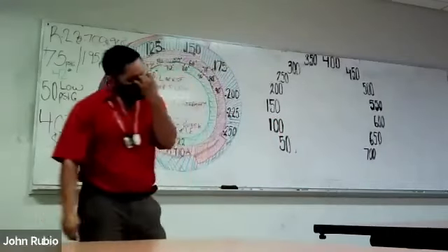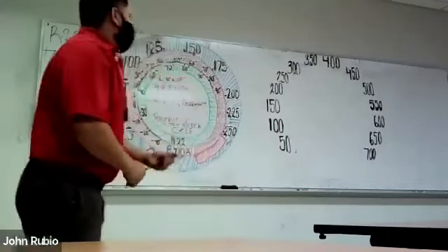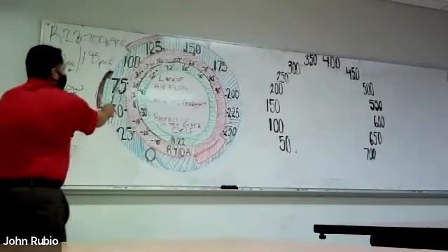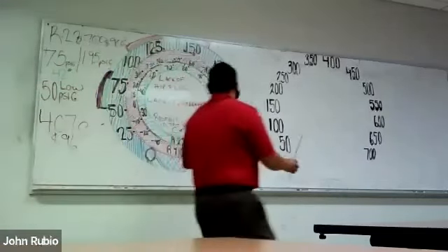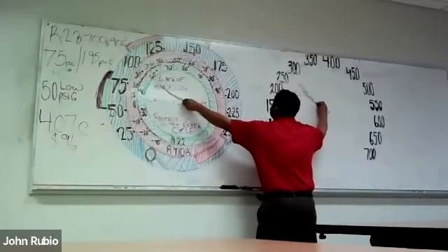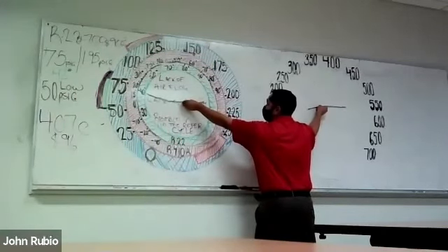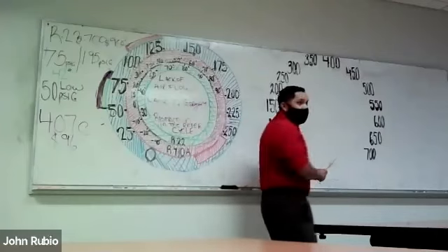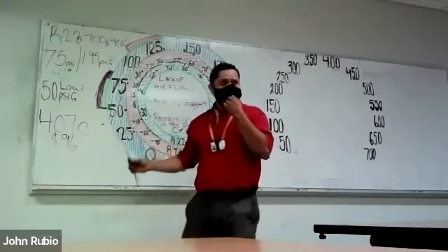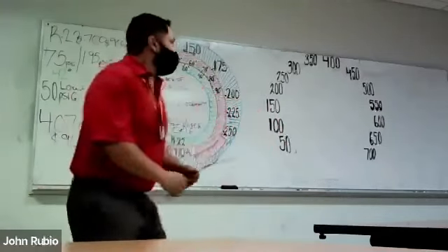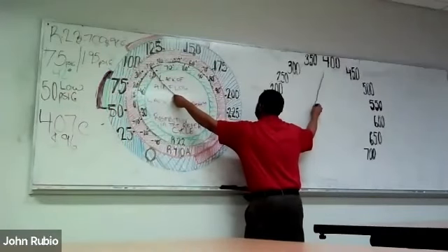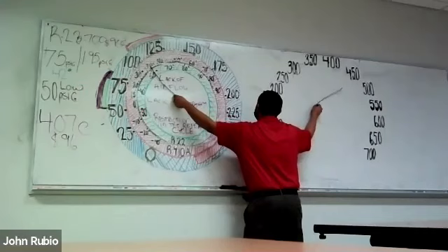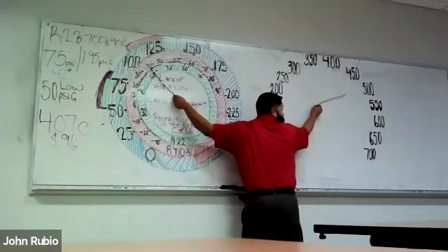That lack of airflow, because there's ice, will bring your low side down. And if you don't have a high side to give you the verification of congruency or not congruency, you're going to miss, and you're going to drop about 6 pounds of refrigerant in this. And if you had a high side, as you're dropping your 6 pounds, you'd peek over and you'd be seeing this happening. But you don't have your high side connected.